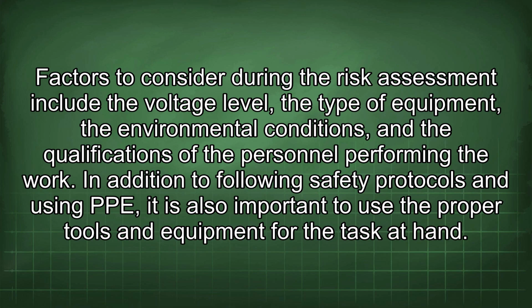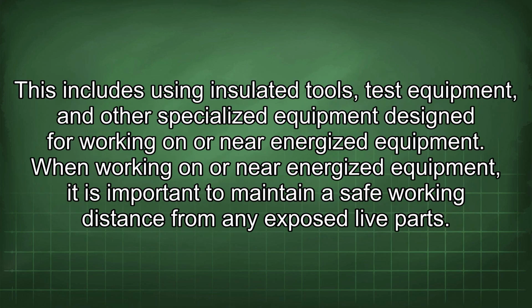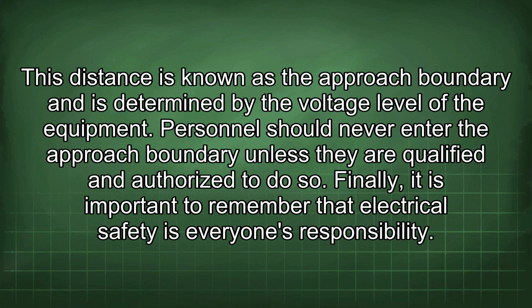In addition to following safety protocols and using PPE, it is also important to use the proper tools and equipment for the task at hand. This includes using insulated tools, test equipment, and other specialized equipment designed for working on or near energized equipment. When working on or near energized equipment, it is important to maintain a safe working distance from any exposed live parts. This distance is known as the approach boundary and is determined by the voltage level of the equipment. Personnel should never enter the approach boundary unless they are qualified and authorized to do so.